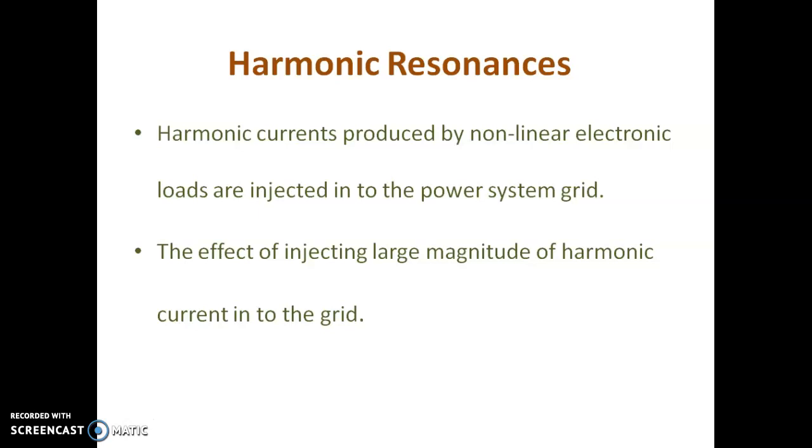The increased capacitance is, however, not the source of harmonic distortion. The harmonic currents may be generated by the units themselves, by local equipment, or by equipment elsewhere. As the current generated by the units does not contain significant low frequency harmonics, the source is most likely found in local equipment.